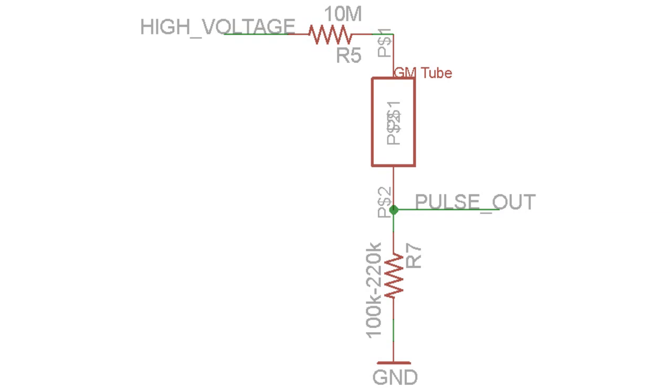When a particle of radiation enters the Geiger-Muller tube, it ionizes the gas inside of it, allowing the high voltage to shoot through from the anode to the cathode. When this occurs, an electrical pulse can be detected between the cathode of the Geiger-Muller tube and the resistor.